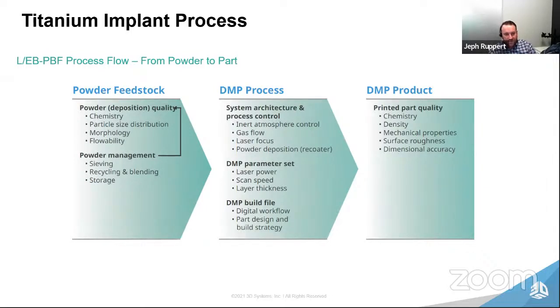Again, this is where, if we're talking about metal printing, titanium has been a strong leader. There's some work in implantable 316. There's a number of devices out there in cobalt chrome, but the vast majority are in titanium, grade 23 titanium, or potentially grade 5 titanium, and occasionally some CP1 commercially pure titanium. But what does that process look like for laser or e-beam powder bed fusion?